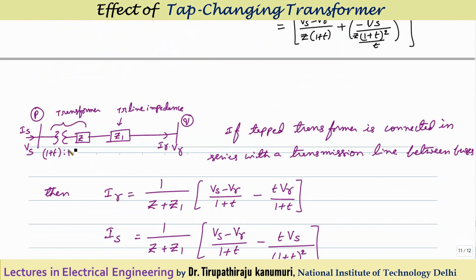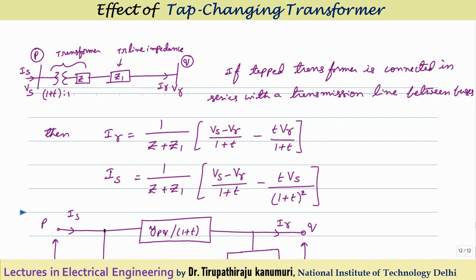Practically, a tap changing transformer is not present alone — a transmission line with per-unit impedance Z1 is also present, either on the primary or secondary side. If the transmission line is on the secondary side with per-unit impedance Z1, and the transformer per-unit impedance is Z, then we simply add the two impedances. Wherever Z appears in the above equations, replace it with Z + Z1.